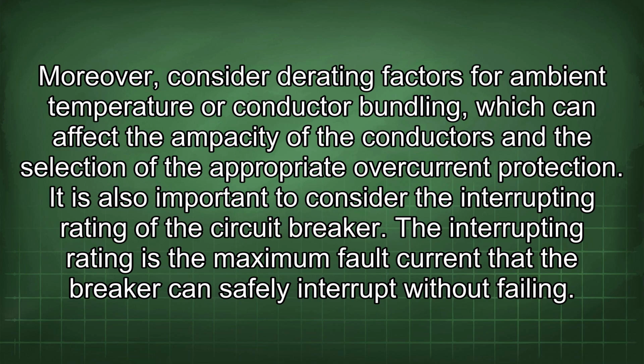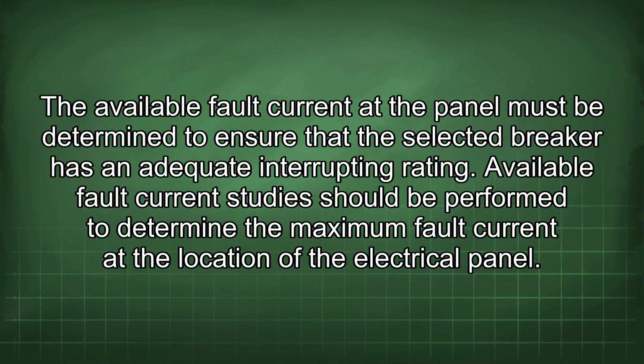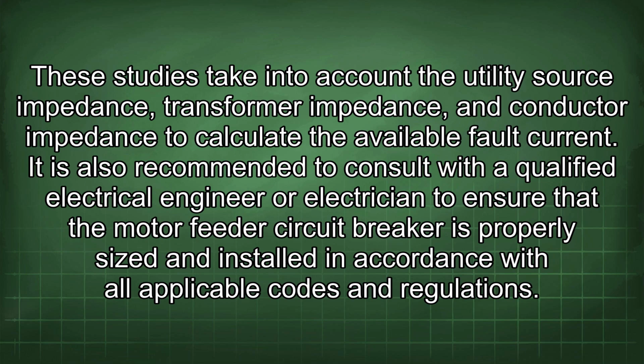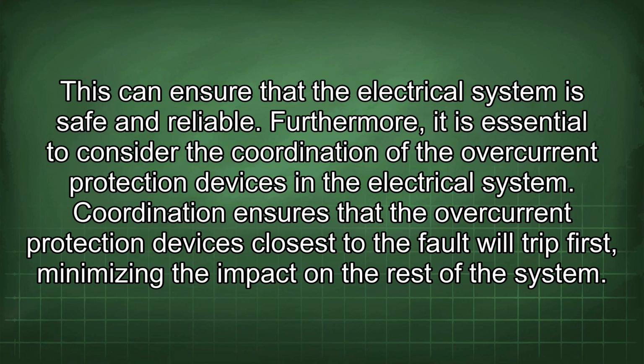It is also important to consider the interrupting rating of the circuit breaker. The interrupting rating is the maximum fault current that the breaker can safely interrupt without failing. The available fault current at the panel must be determined to ensure that the selected breaker has an adequate interrupting rating. Available fault current studies should be performed to determine the maximum fault current at the location of the electrical panel. These studies take into account the utility source impedance, transformer impedance, and conductor impedance to calculate the available fault current. It is also recommended to consult with a qualified electrical engineer or electrician to ensure that the motor feeder circuit breaker is properly sized and installed in accordance with all applicable codes and regulations. This can ensure that the electrical system is safe and reliable.